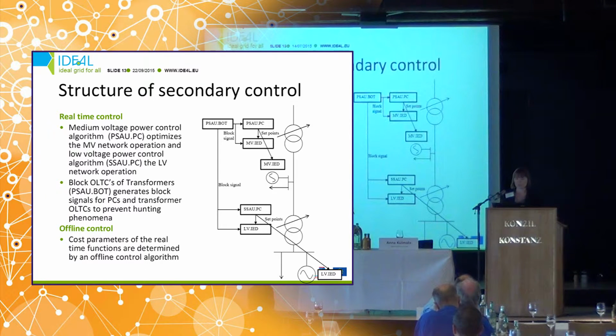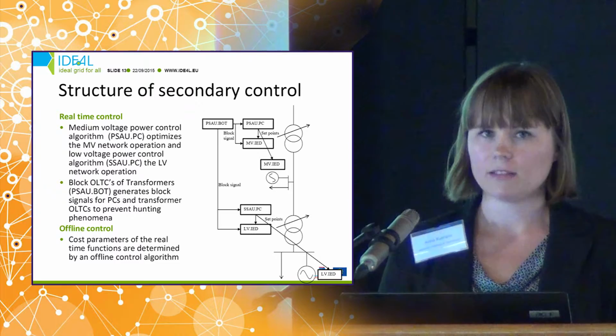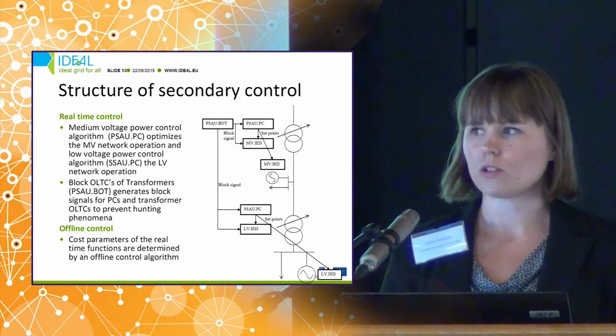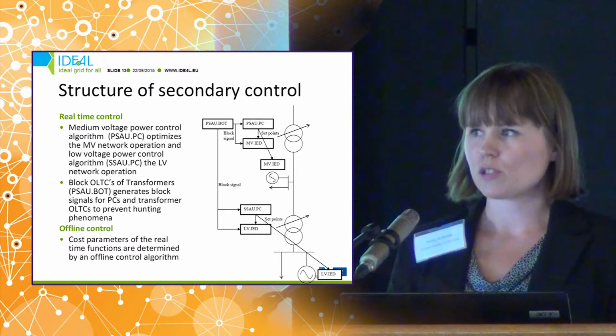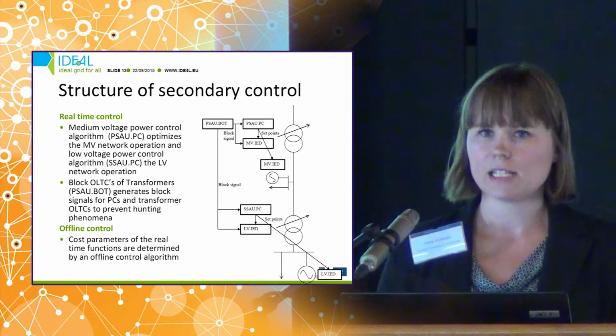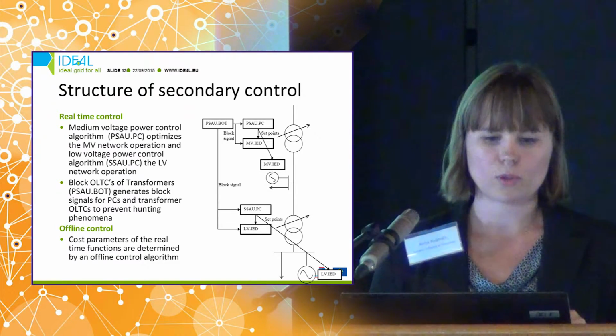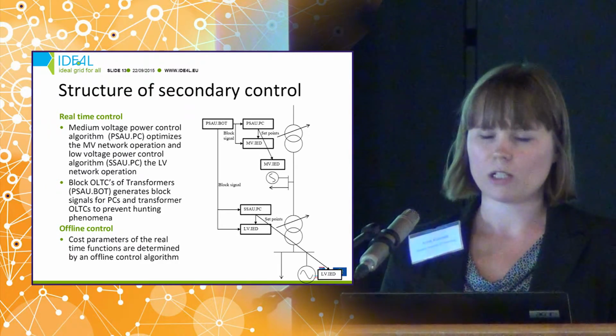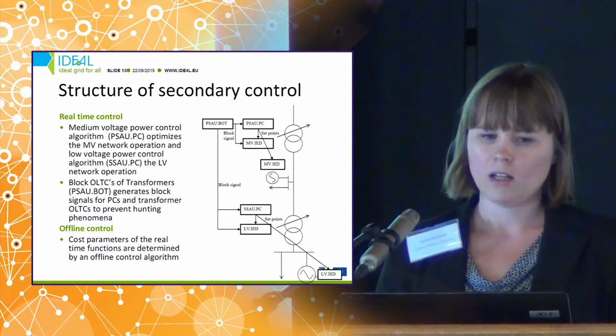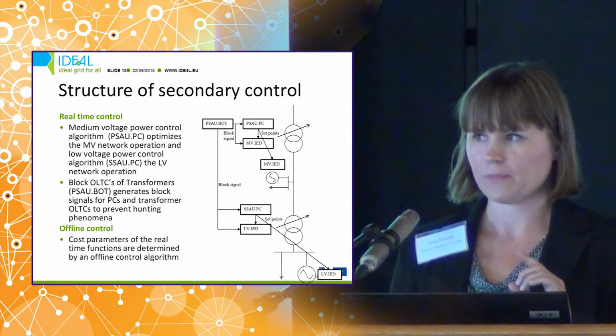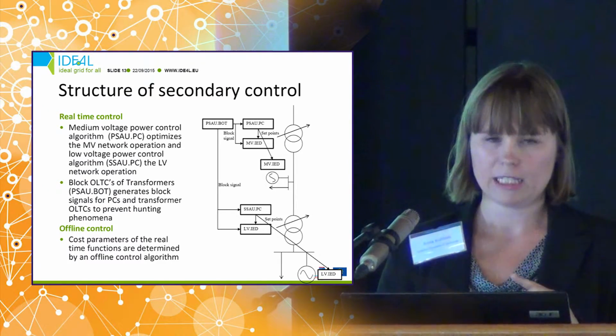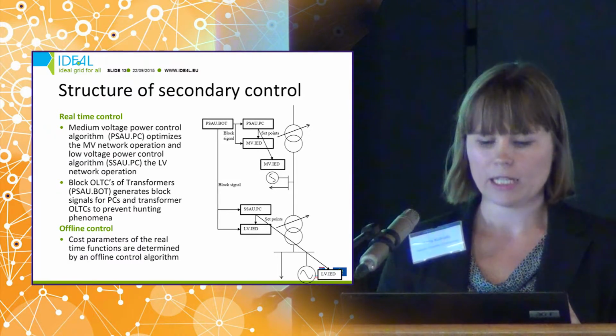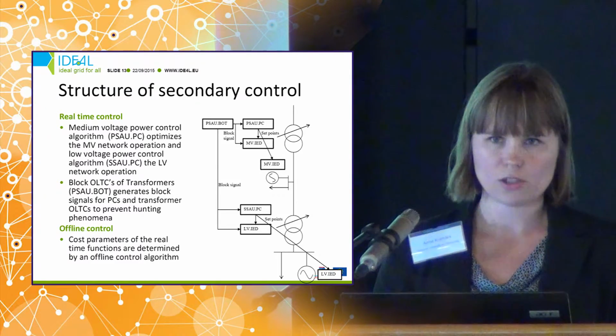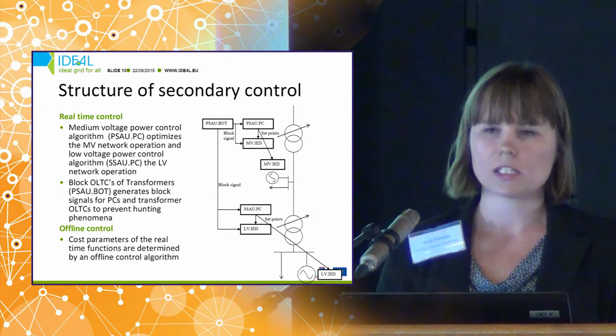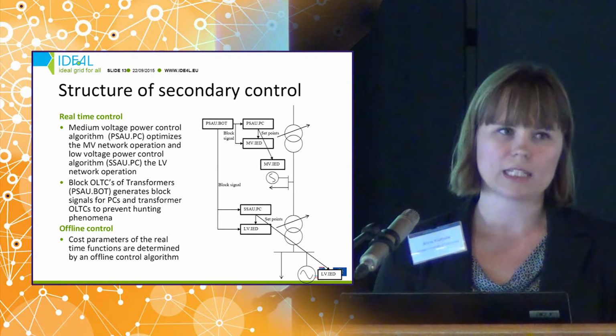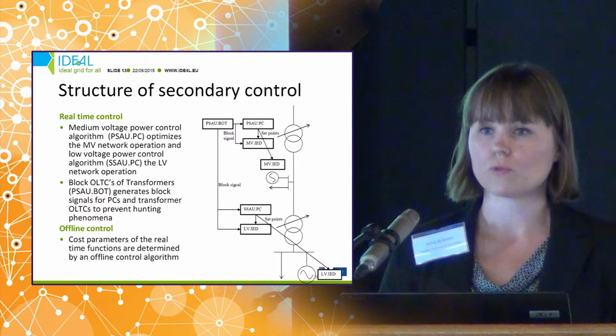The structure of the secondary control is shown in the picture. So as I previously said, the power control algorithm located at the primary substation automation units is responsible for controlling the medium voltage network. So it sends set points only to resources connected to the medium voltage network, and the secondary substation automation unit power control algorithm controls the low voltage network. The real-time control consists of these power control algorithms that are calculating an optimal state for the network and mitigating the congestions. And then we have added a BOT unit that is used to prevent hunting of transformer OLTCs if there is a tap changer also at the distribution transformer.